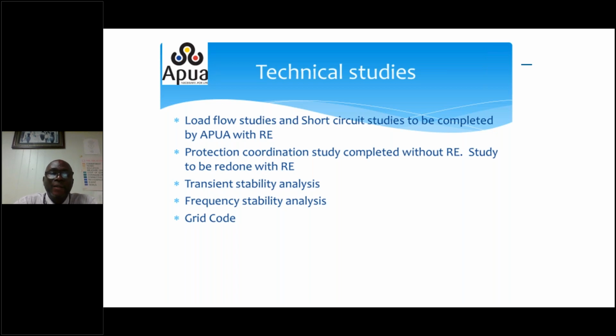We have an interconnection policy I mentioned before. It's quite aggressive. We have basically ensured that only 15% of renewable will go on any feeder, and that is to ensure that we don't have situations with poor quality issues on any system. We have also ensured that any new generation that we have, I speak of the LNG plant, we have in plan green, first of all, as green as we can go, obviously. I mean, LNG is not green, but it's one of the greenest sources of fossil fuel. And the controls, we ensure that the controls are flexible enough so that the plant can adjust to the varying frequency as a result of the VRE.